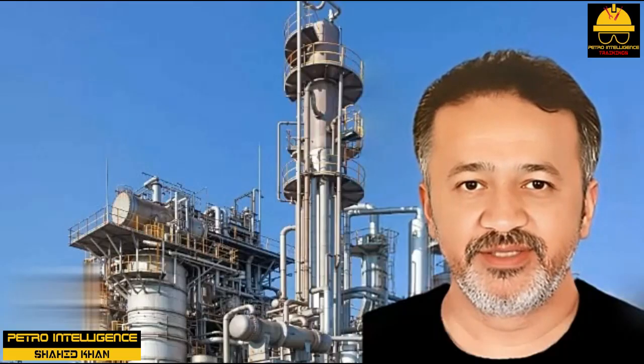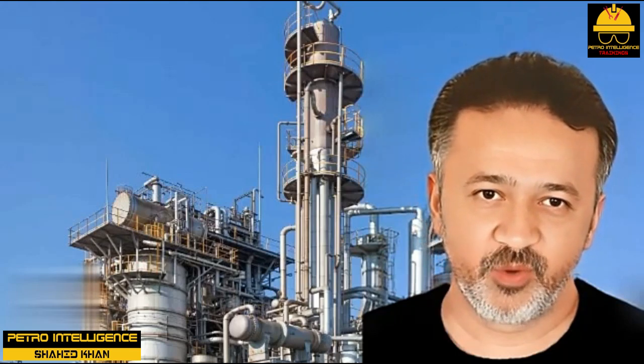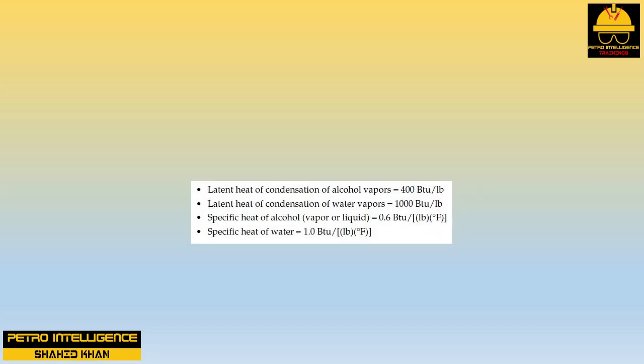For heat balance calculations, if you have listened to my previous lectures and understood what you have heard, you will readily understand the following calculation. It is simply a repetition with numbers of the discussion previously presented. You will require the following values: latent heat of condensation of alcohol vapors = 400 BTU/lb; latent heat of condensation of water vapors = 1000 BTU/lb.